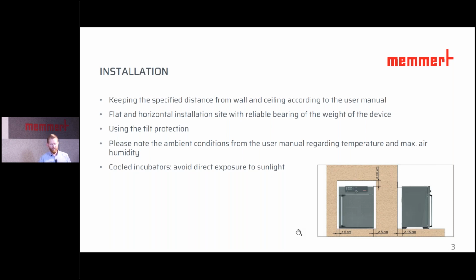A level and horizontal surface is important to ensure that no liquids can leak from the vessels, from the probes placed in the unit. Many appliances are supplied with a tilt protection. This should also be used under all circumstances to secure the appliance to the wall and thus to reduce the risk of tipping over when the door is opened.